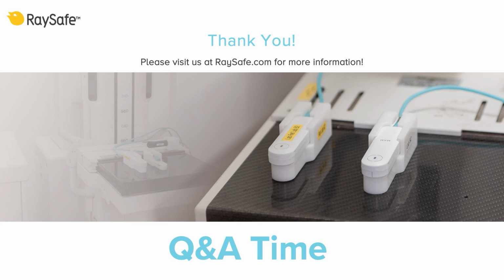And depending on whether you have the P or the B version, I would say that the 452 also has a better energy response graph. The 451P, for example, has a low energy response for low energies in the mammography area, while the ambient 452 is very flat around 1 at lower energies. And the 452 has better data capability when it comes to storing and analyzing the data. Those are, I guess, the main takeaways between the 451 and the 452.